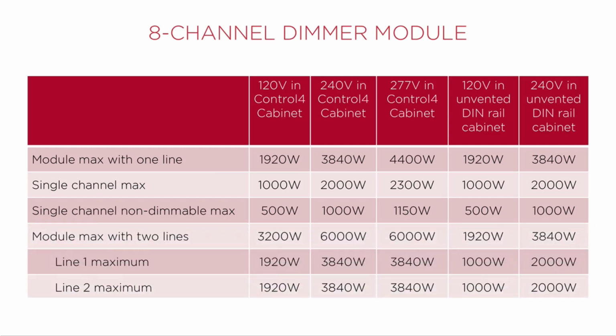However, if used with two lines at 120 volts each, the maximum is 3,200 watts. There is a maximum wattage of 1,920 watts per line. Again, those numbers double if used with 240 volts. Notice that if they are used in a non-Control4 unvented DIN rail cabinet, there is a decrease in the maximum wattage due to the potential for overheating.